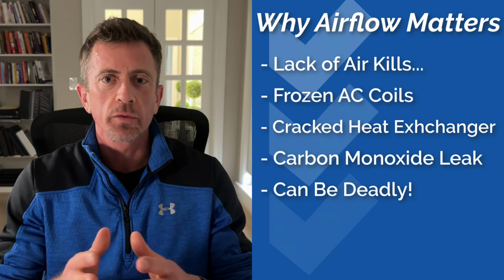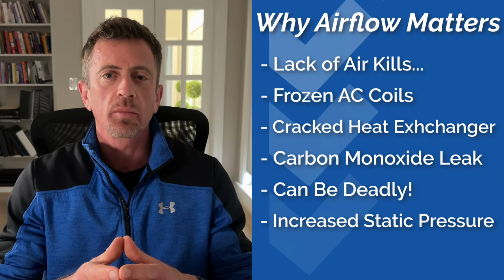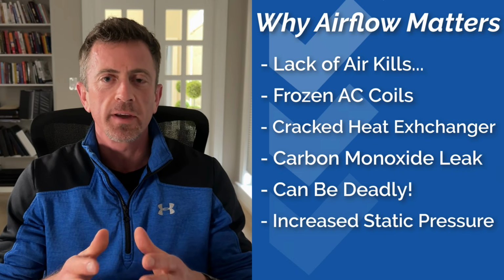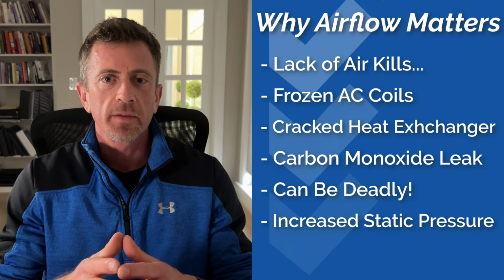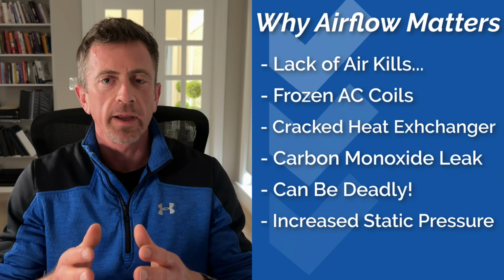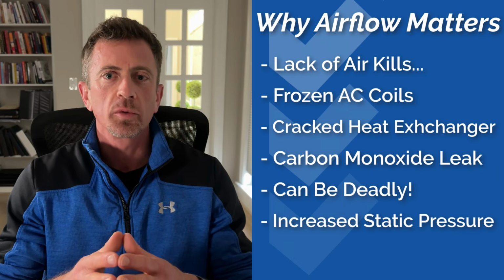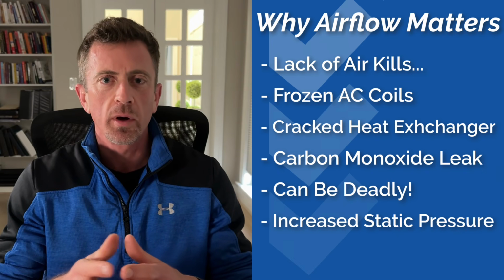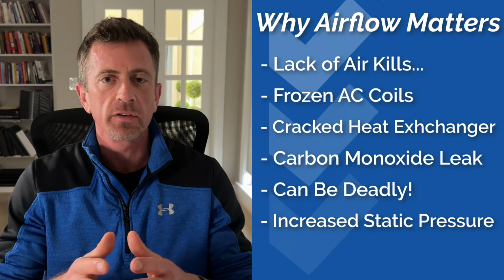Furthermore, when airflow is restricted, it increases the static pressure inside your ductwork and your HVAC equipment. We talked about this in chapter 7, but it's worth reiterating here. High static pressure puts extra strain on your system's blower motor, reducing its lifespan and efficiency.